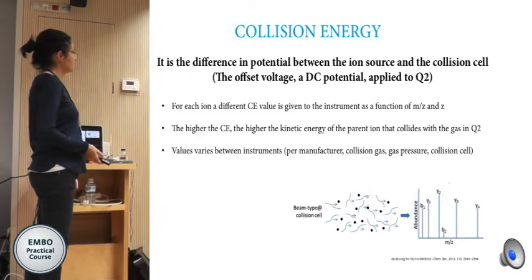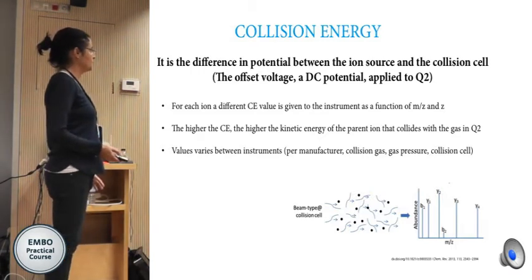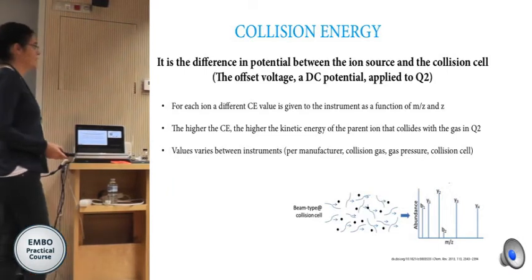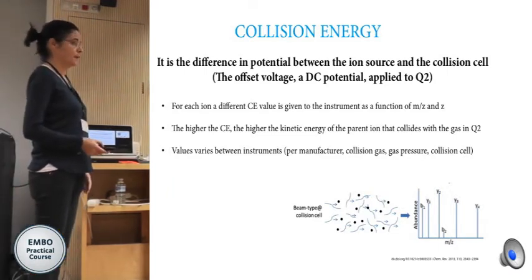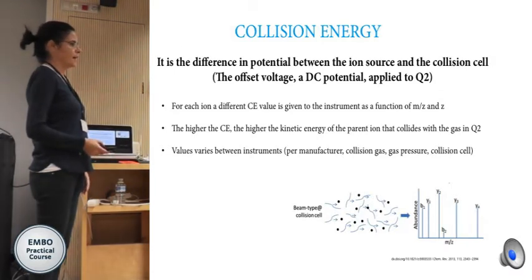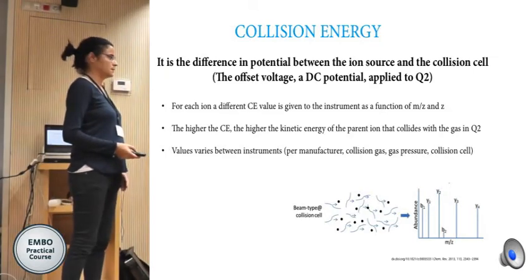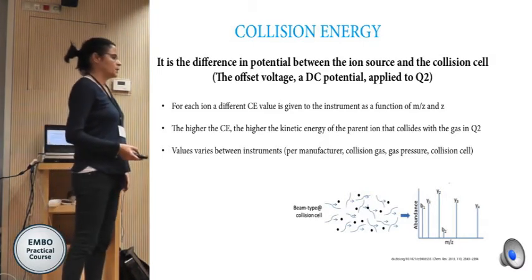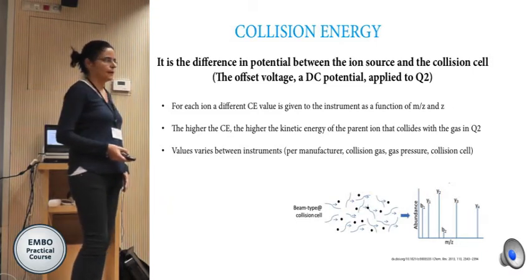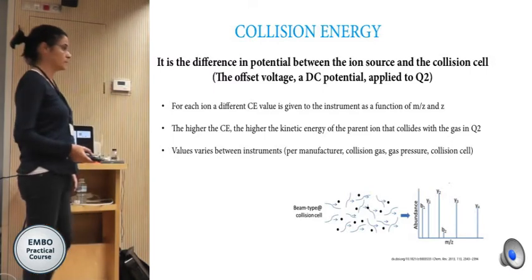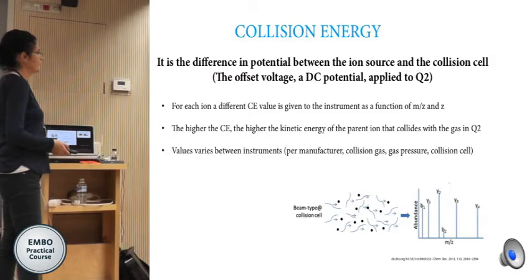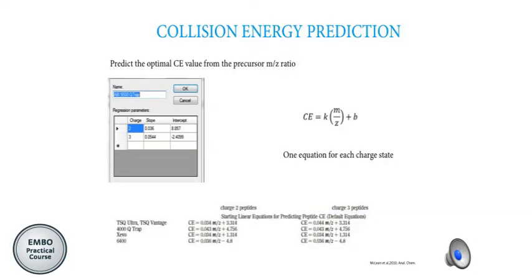You need to know that these optimizations can be done and in a particular case can be useful. The collision energy is a difference of potential that we use to break the peptides, and for each peptide, Skyline for example gives a different value for collision energy that depends on the mass and on the charge. The higher the energy, the more the peptide breaks, and the values can vary between manufacturers. It can also depend on the collision gas, the pressure of the gas, and the design of the collision cells.